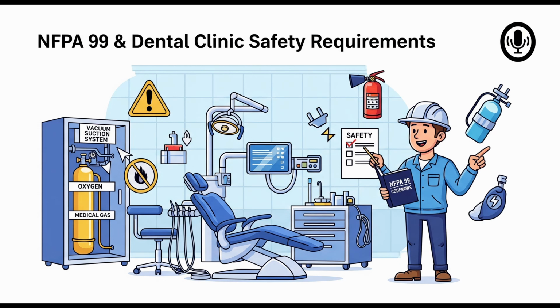That was, wow, a really detailed exploration of the code. Yeah. It makes it so clear that NFPA 99 requires a serious engineered approach to safety, even in a setting like a dental clinic that might seem less complex than a hospital. It really does. It highlights that patient safety relies on this underlying infrastructure being robust, correctly installed, and meticulously maintained, regardless of the facility size. That risk-based approach means you can't just assume lower requirements, you look at the procedure risk, and the systems have to match. And it seems zeroing in on those Category 3 requirements is the critical first step for navigating this code in the dental world. Precisely. Understanding you're likely in Category 3 for these pipe systems, and then working through the specifics in sections like 5.3 and 15.4 for the gas vacuum, Chapter 11 for storage, Chapter 6 for electrical, that's the path.